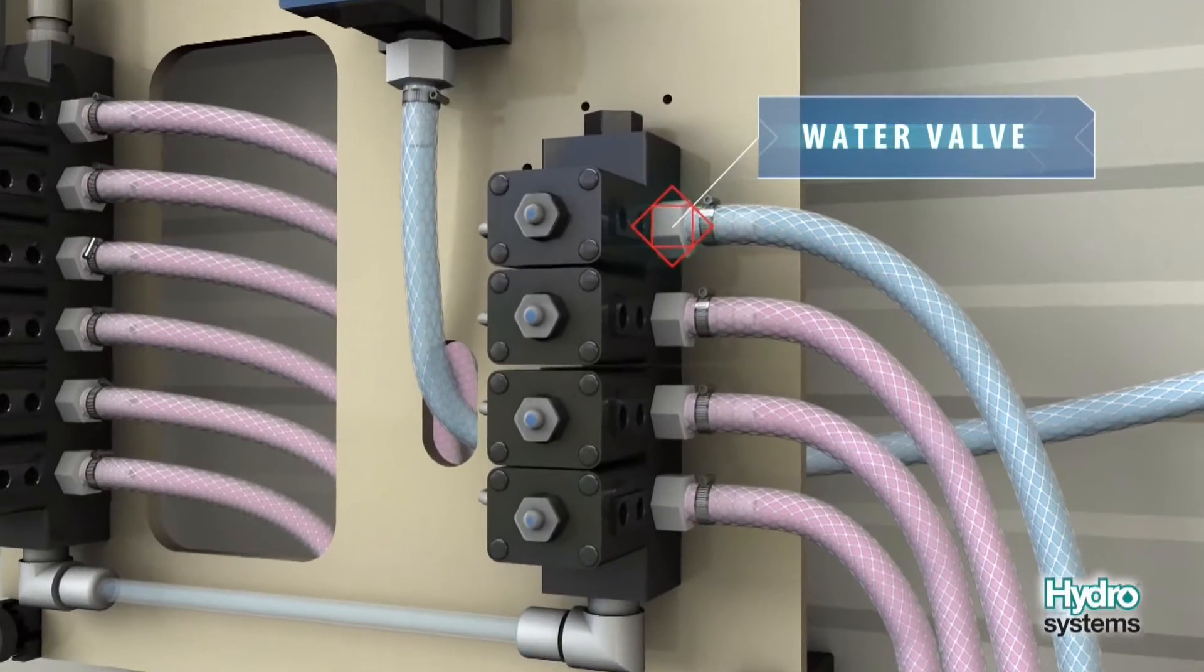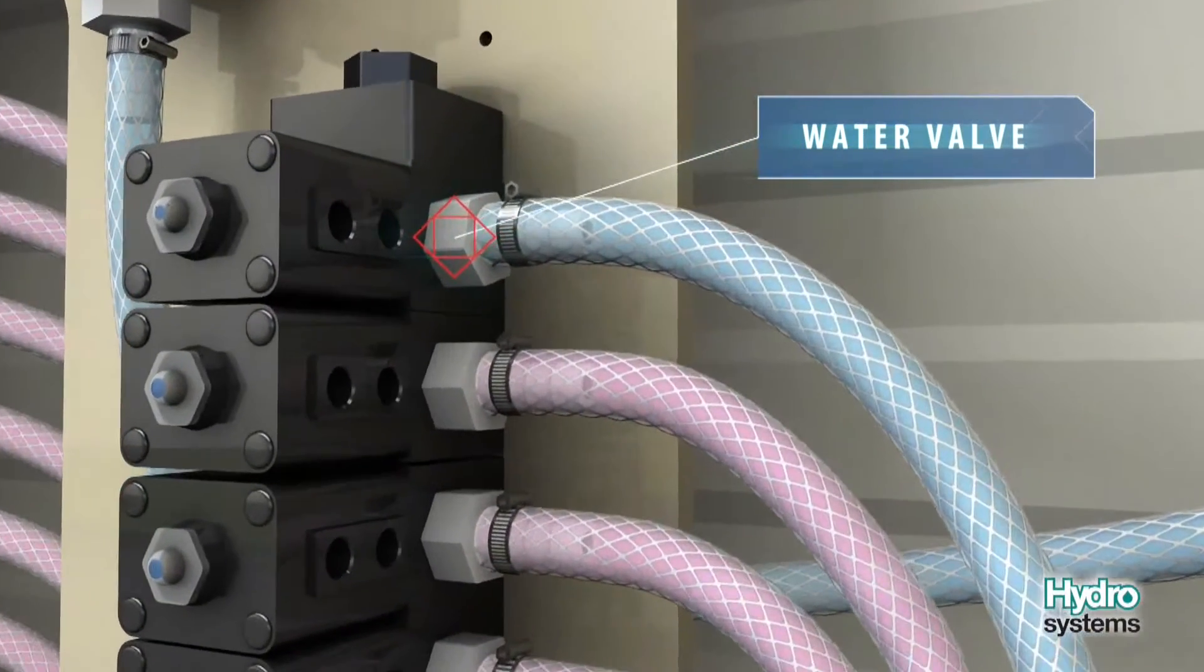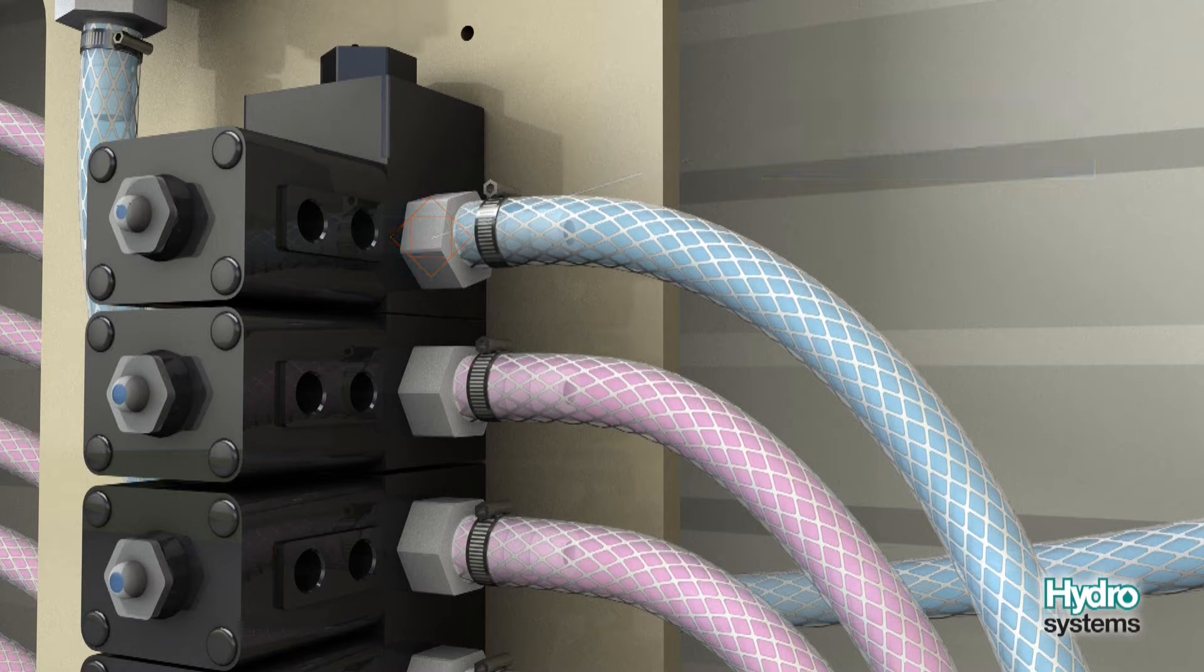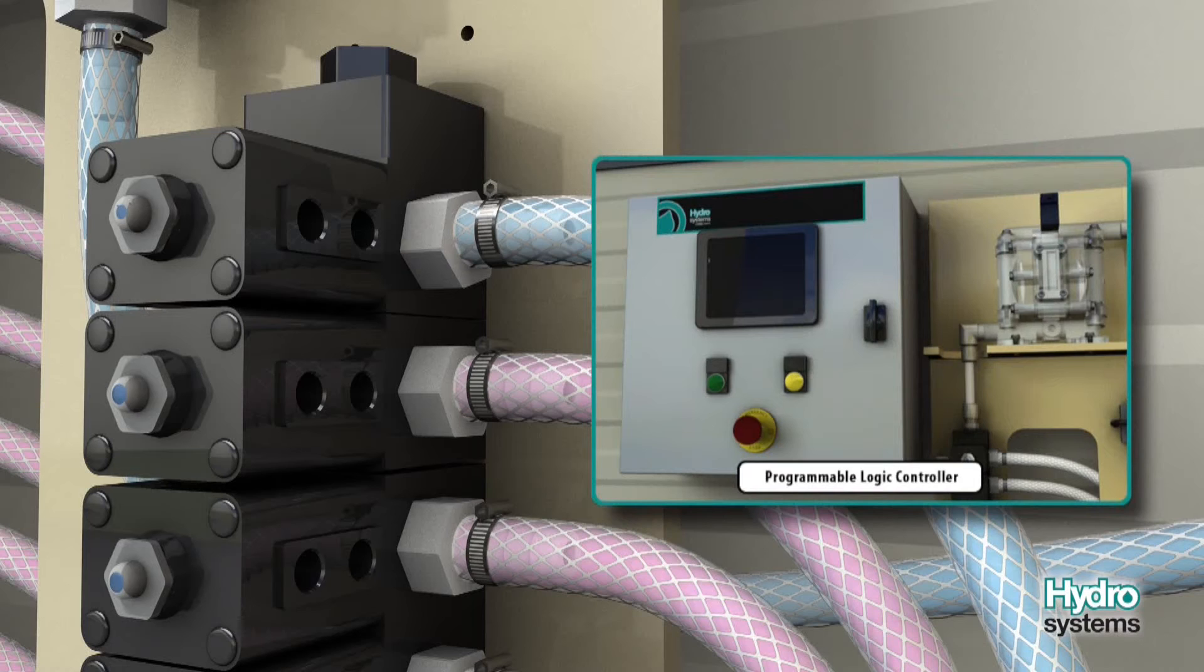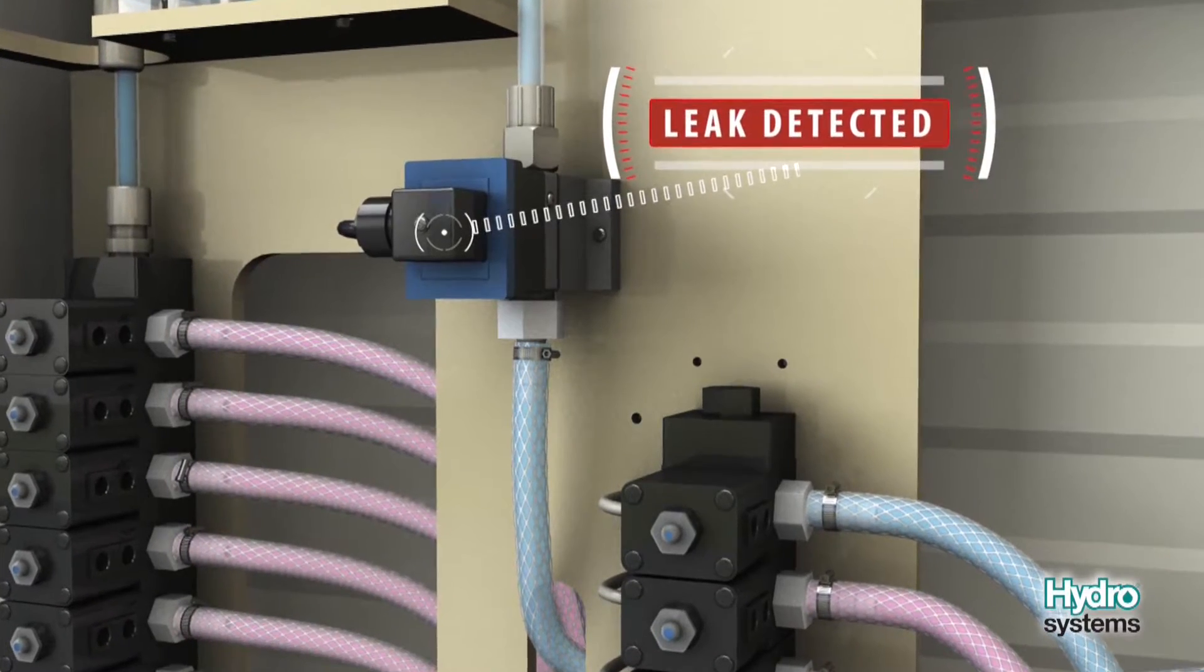During the leak test, the water valve opens at the collector which pressurizes the channel, while the product valves and the distributor valves remain closed. If the Programmable Logic Controller detects pulses from the flow meter, that means there is a leak and the dosing is aborted.